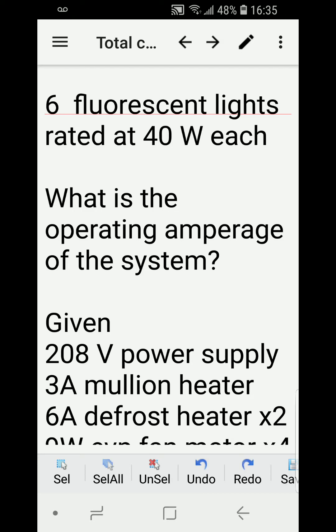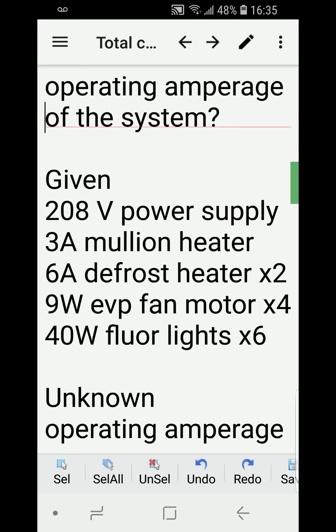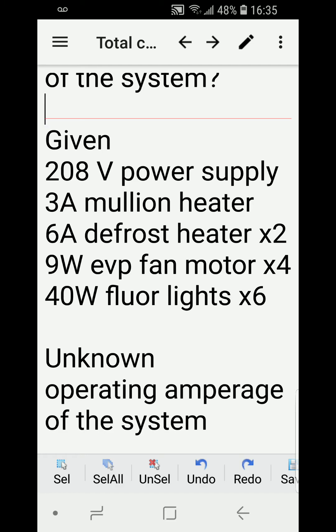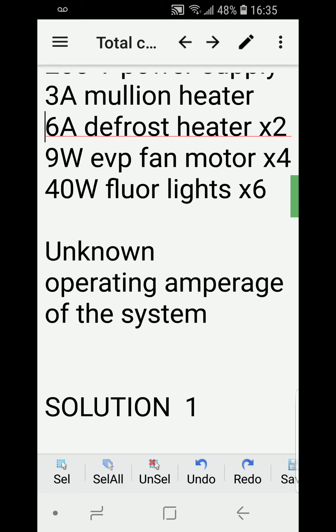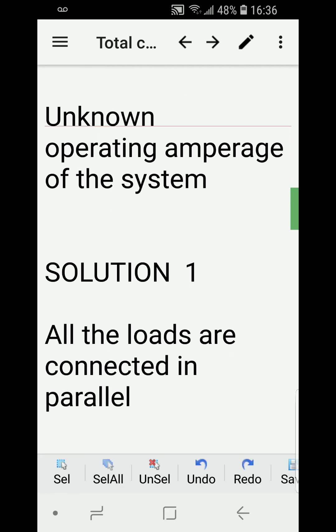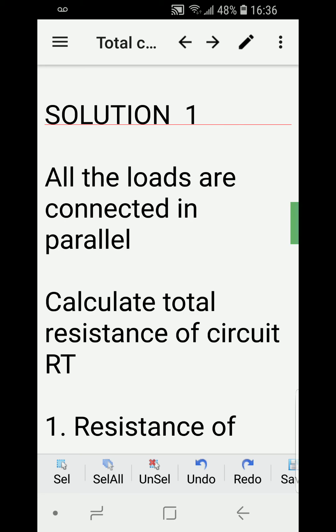The question asks for the operating amperage of the system. Let's list the given values: 208 volts as the power supply, 3 amperes for the mullion heater, 6 amperes for the defrost heaters times 2, 9 watts for the evaporator fan motors times 4, 40 watts for the fluorescent lights times 6. The unknown is the operating amperage of the system.